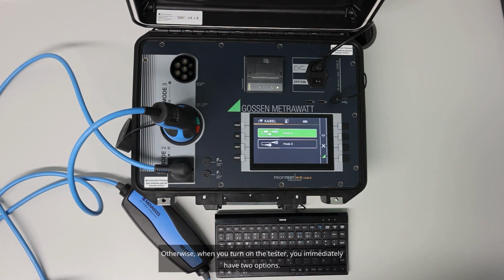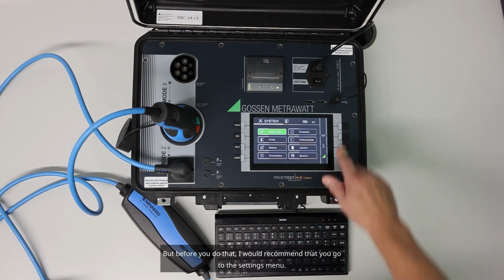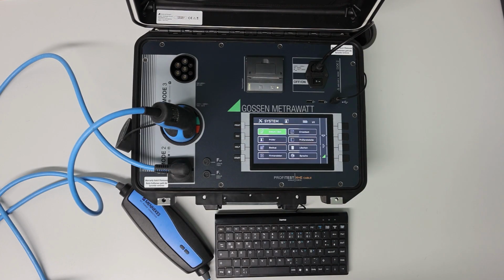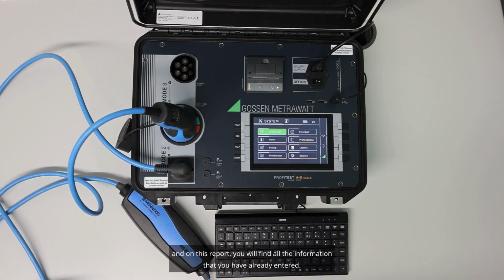Otherwise, when you turn on the tester, you immediately have two options. In the database, you select either the appropriate Mode 2 or Mode 3 charging cable for testing. But before you do that, I would recommend that you go to the Settings menu. Because in the end, you want to have a report, and on this report, you will find all the information that you have already entered.